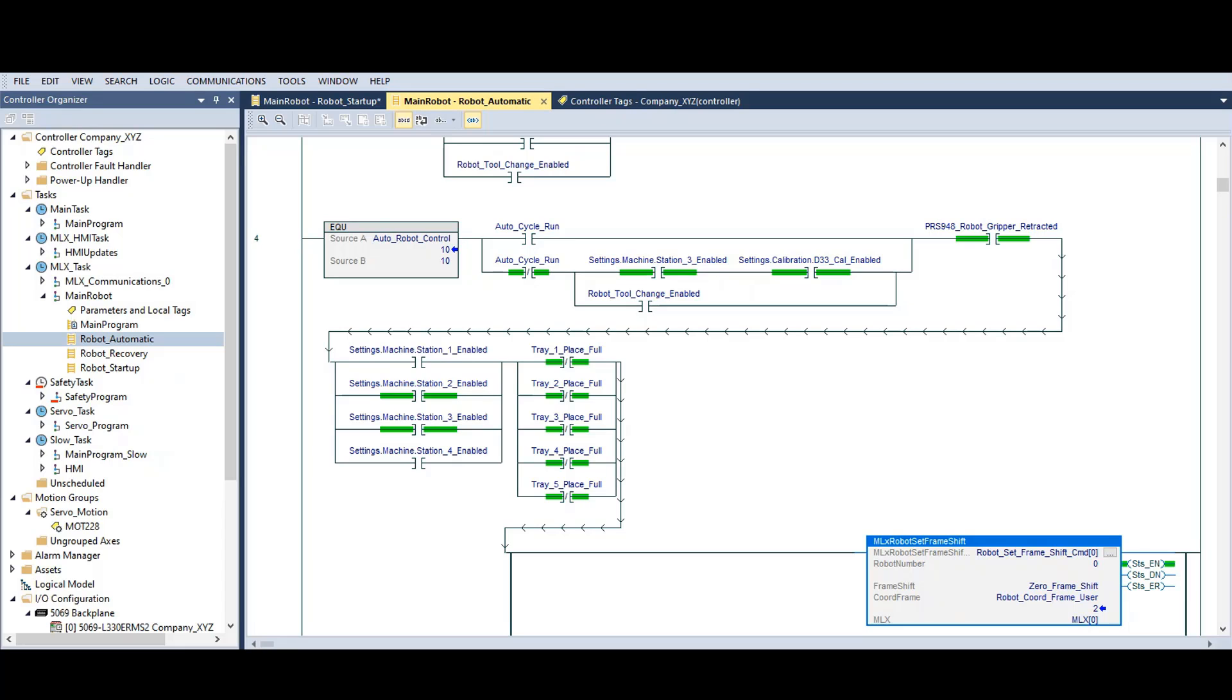The most likely reason for this is the previous AOI command was disabled before it was finished. There are two options to find the previous AOI. The first option is to backtrack through the steps and determine the last MLX AOI that was commanded. This is the easiest option, but not when the ladder is very complex or you're not familiar with the programming.